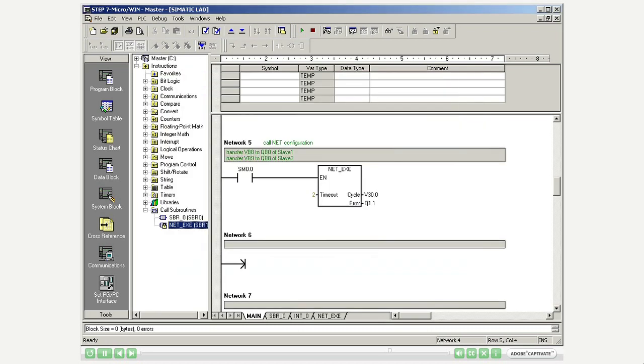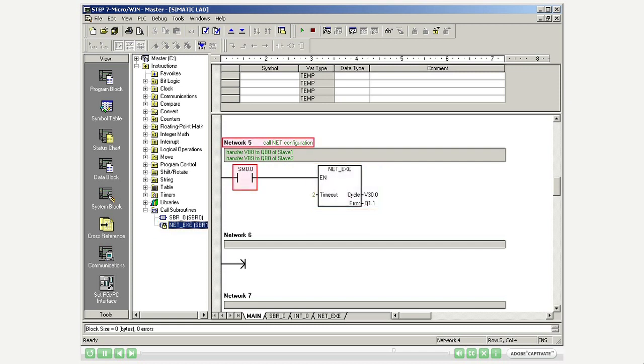Call the subroutine NetExec generated by the instruction wizard every scan cycle in network 5. As timeout you select 2 seconds, assign a free variable address for the cycle bit, and display communication errors at output 1.1.